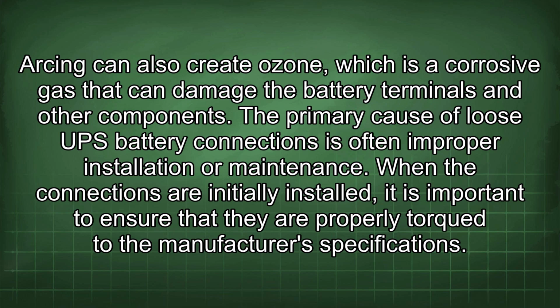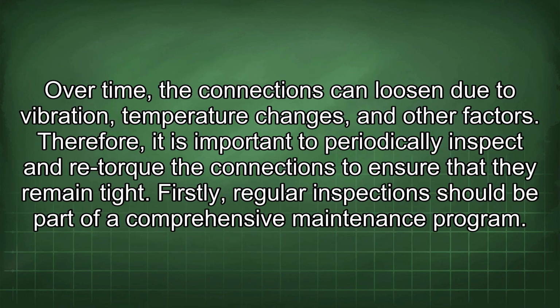The primary cause of loose UPS battery connections is often improper installation or maintenance. When the connections are initially installed, it is important to ensure that they are properly torqued to the manufacturer's specifications. Over time, the connections can loosen due to vibration, temperature changes, and other factors. Therefore, it is important to periodically inspect and retorque the connections to ensure that they remain tight.